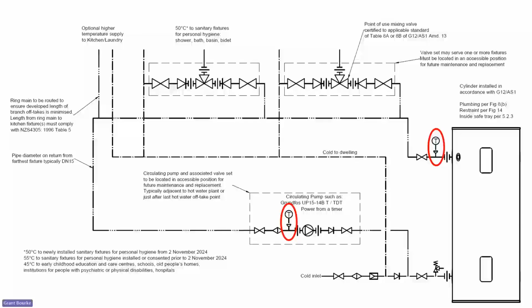What can I say politely about this? It's really handy to have temperature measuring positions on ring mains. There's a compliance requirement about the ring main return temperature that it needs to be higher than 55 degrees.